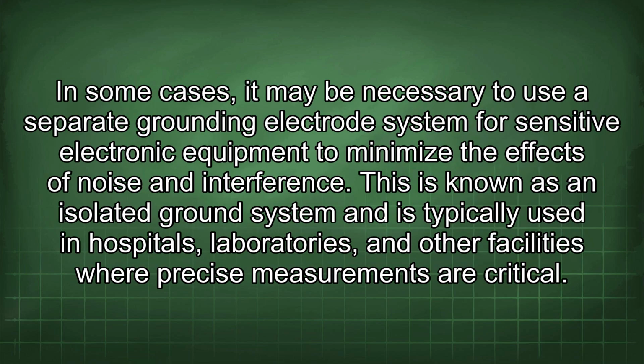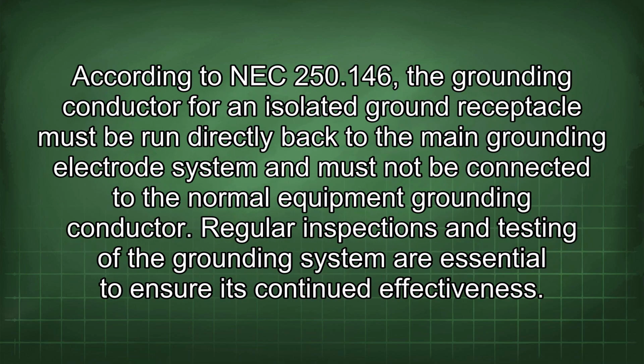In some cases, it may be necessary to use a separate grounding electrode system for sensitive electronic equipment to minimize the effects of noise and interference. This is known as an isolated ground system and is typically used in hospitals, laboratories, and other facilities where precise measurements are critical. According to NEC 250.146, the grounding conductor for an isolated ground receptacle must be run directly back to the main grounding electrode system and must not be connected to the normal equipment grounding conductor.